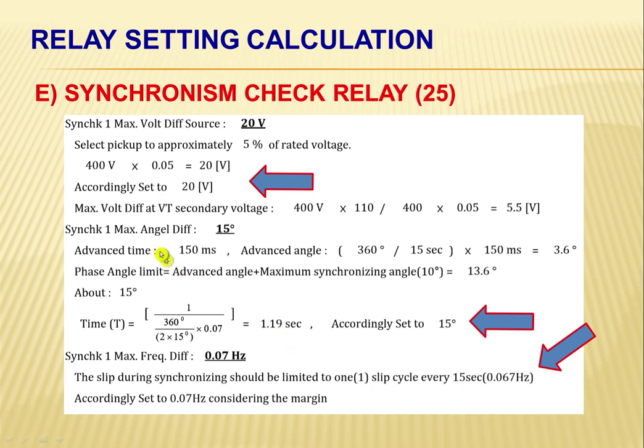Let's come back to the maximum angle difference. This is 15 degrees here. According to the Buff Book, ANSI IEEE 242, the closing angle should be at most 20 degrees. So we are okay here because our maximum angle difference being calculated is 15 degrees only.